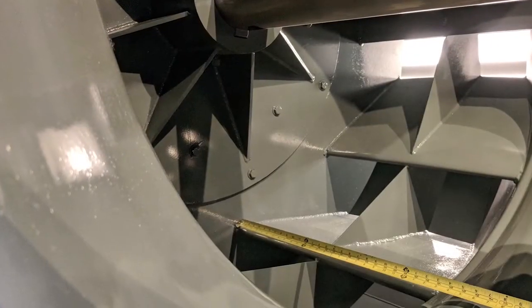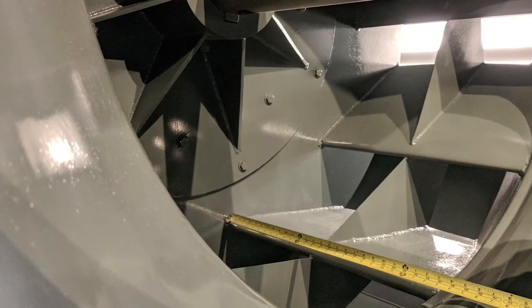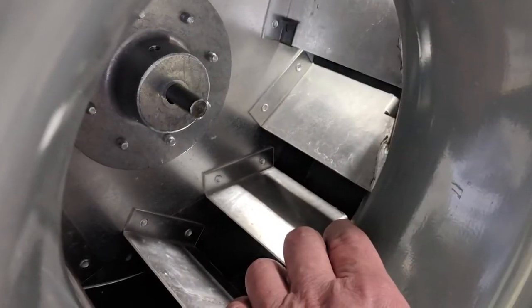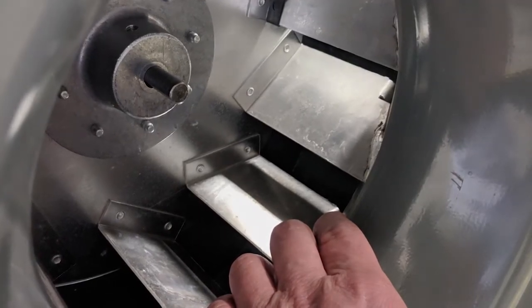Before hooking up ductwork to the inlet of a centrifugal fan, it's always a good idea to check the wheel to inlet fit as it is difficult to check later and even more difficult to diagnose from fan performance data. Let's see why.